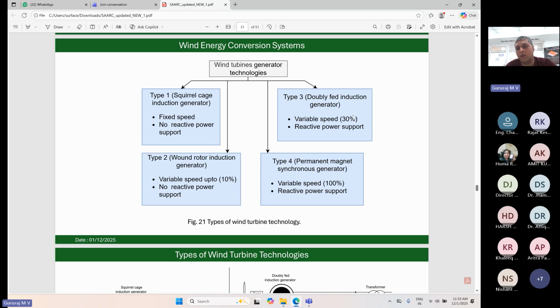The most popular one, which is widely adopted across the globe, is the type 3 generator, famously called the double-fed induction generator. The name itself suggests that generation takes place from both sides, stator and rotor. The sweet spot of rotor speed variation is around plus or minus 30%, because for most turbines and site conditions, the wind speed varies in this range. So the converter size required would be much smaller, and cheaper, as compared to type 4. This makes it a more economical solution, and MPPT mode of operation and reactive power support are all quite possible in these type 3 generators.